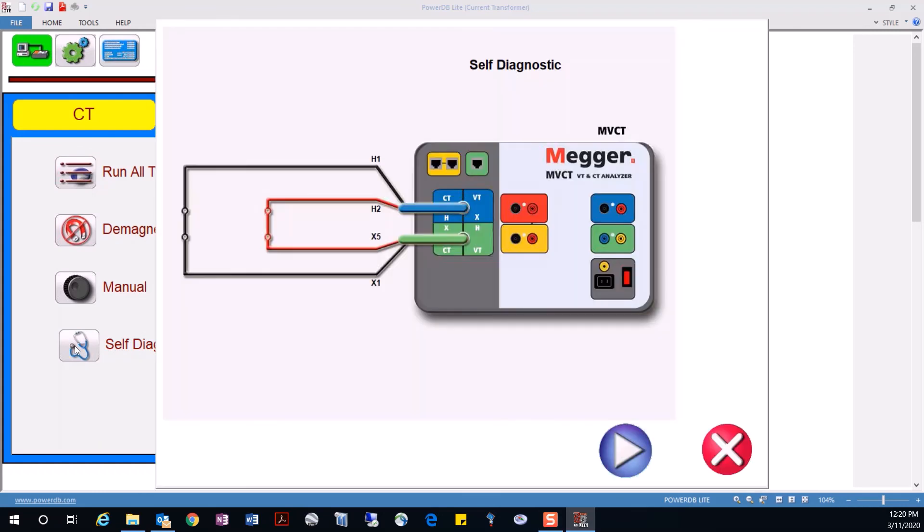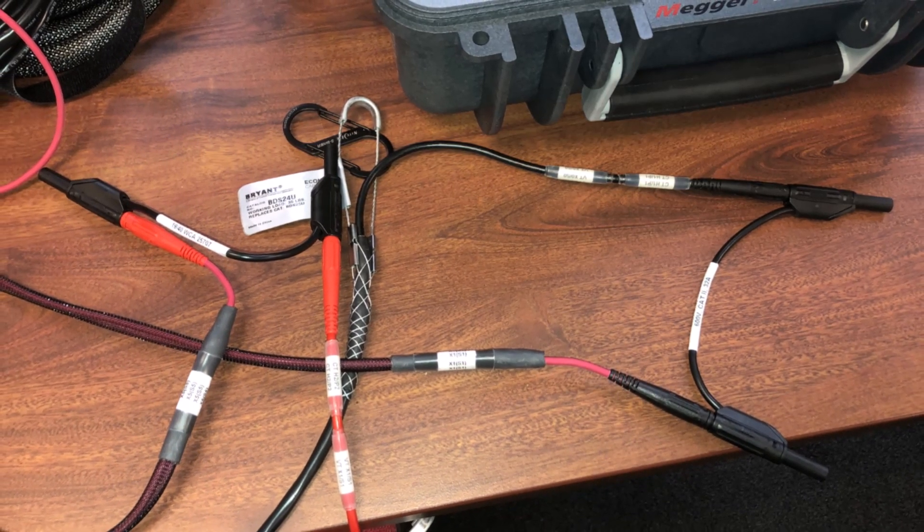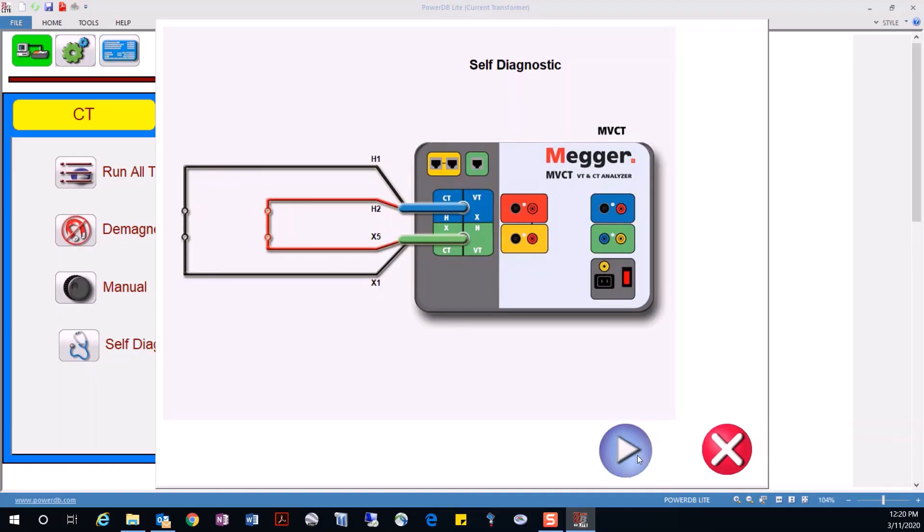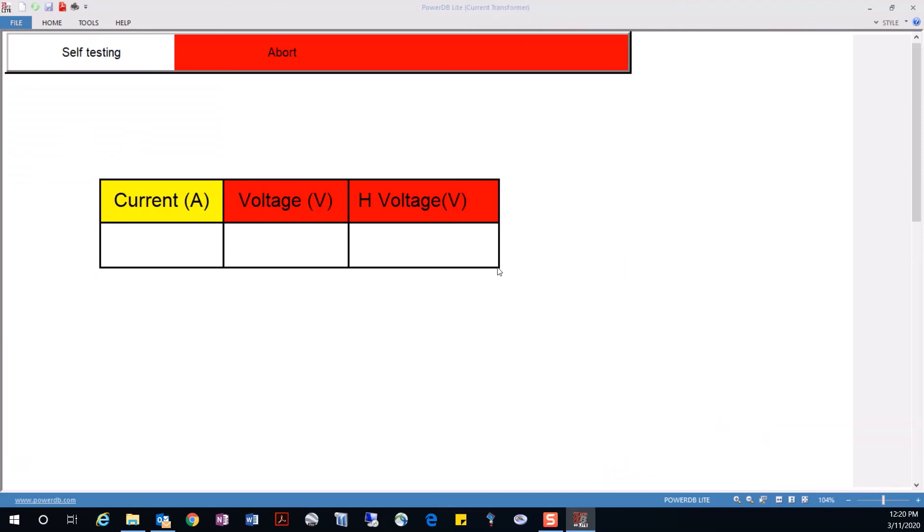Finally, the MVCT testing set has the capability of running self-diagnostics. We select the option from the main menu and confirm correct connection of the testing leads. This self-diagnostic check ensures that the unit internal voltage and current generators and meters are working properly. This diagnostic check should be run before and after each testing session to ensure personal safety and valid testing results.